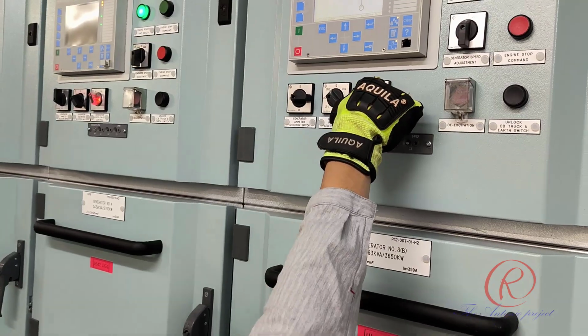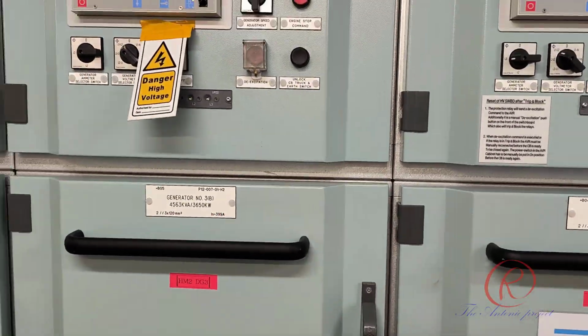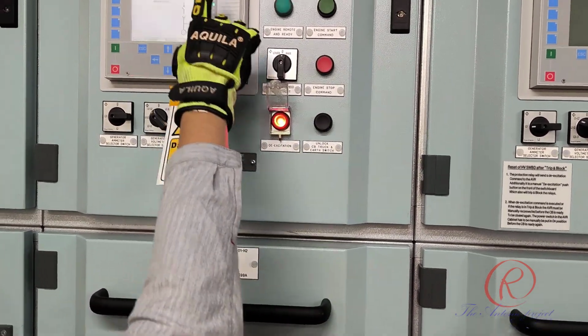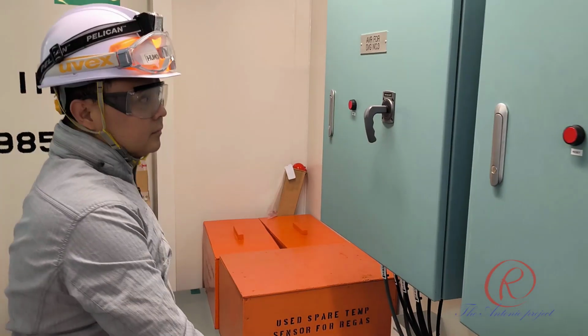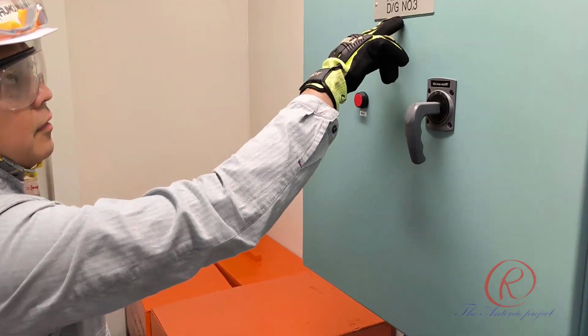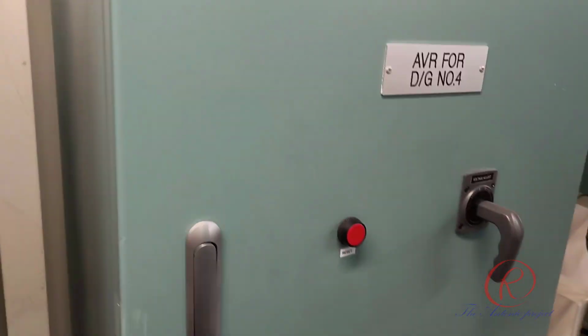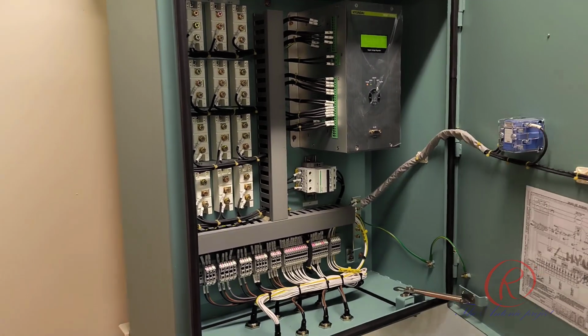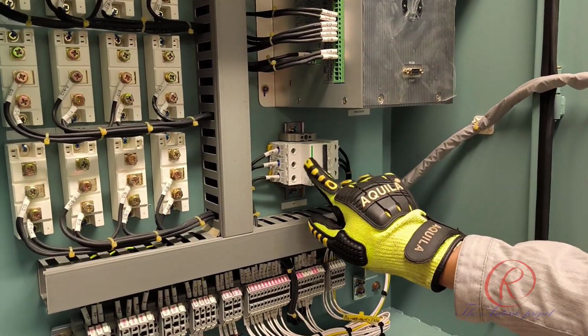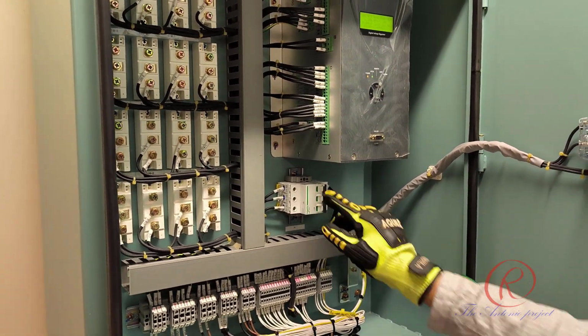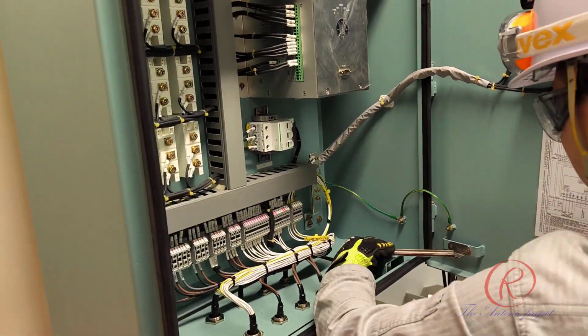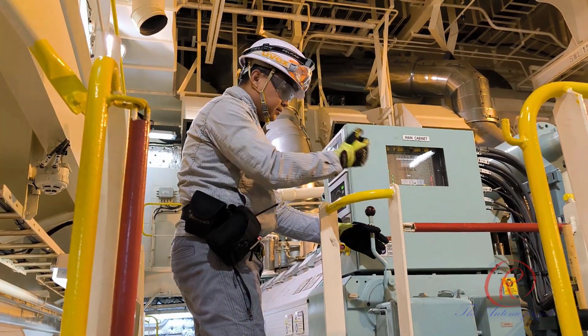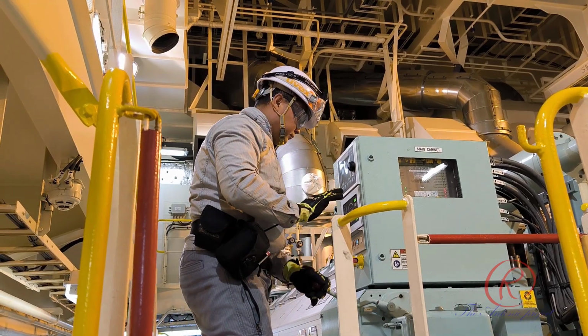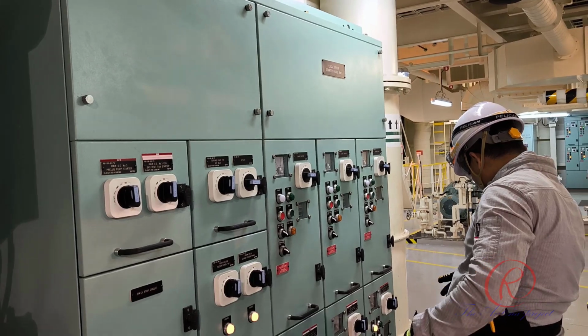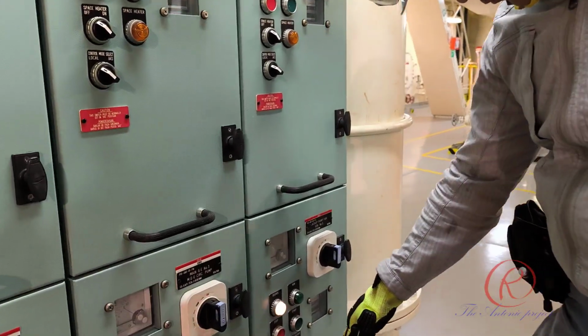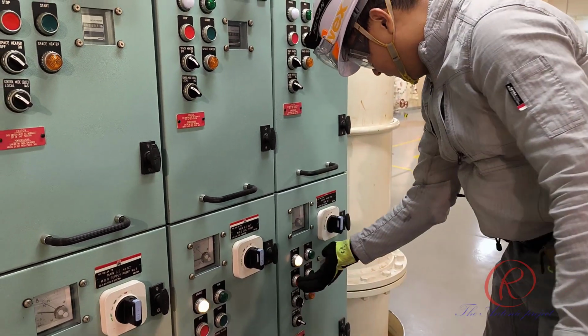Alternator capacitor to be powered off. Activate the de-excitation. Make sure that the number of DG is correct. This one, number 3, becomes number 4. So we will break off the AVR. This power is to be broken off. Next is to secure the main generator engine. Set the fuel lever to stop, switch control position to local, and make sure the stop lamp is on. Stop and secure the jack up pump.